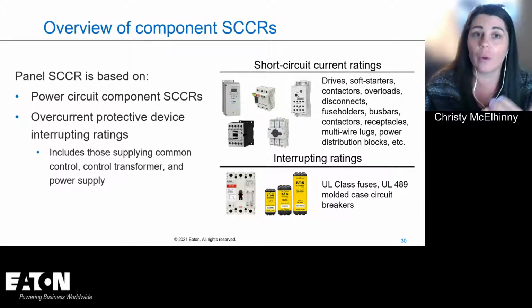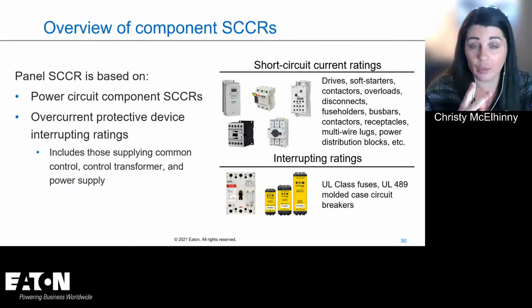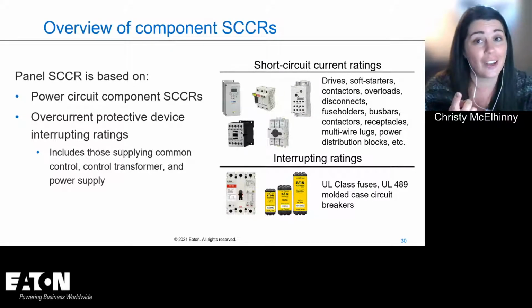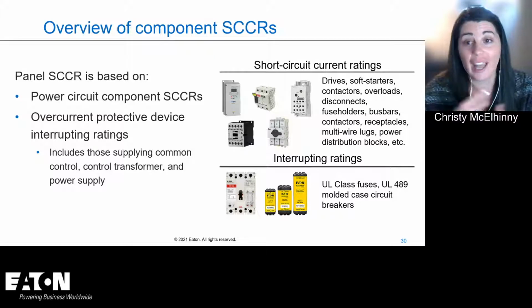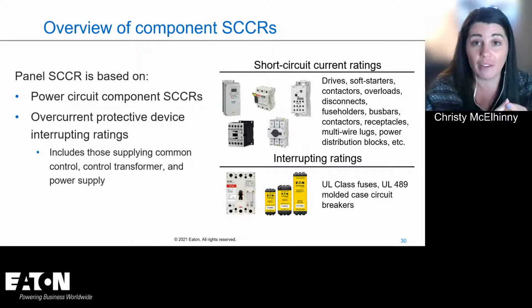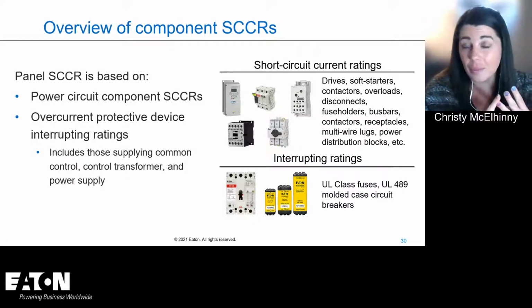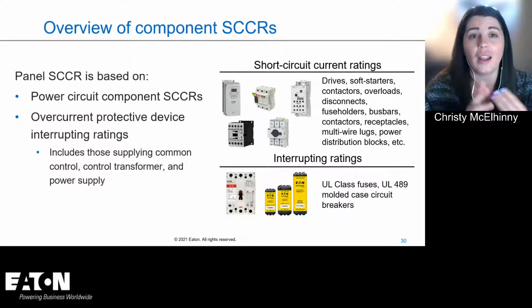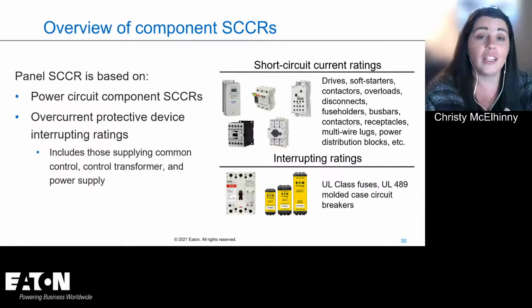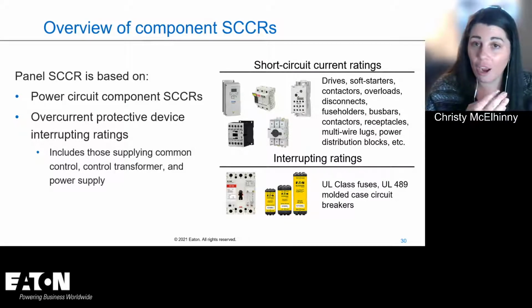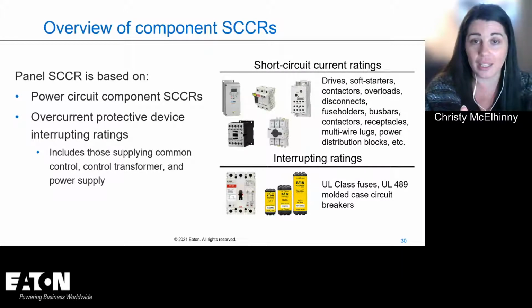So it's all of the power circuit components, those that feed loads. And they're going to have two ratings that we care about when we try to determine the short circuit current rating of a panel. It's going to be SCCR ratings or interrupting ratings. Now, we should already know the difference between these, but a refresher, right? Interrupting rating applies to my fuse, to my breaker, sometimes something like a manual motor protector inside an industrial control panel. That's the device that's interrupting the current. And it's really important to note that, by definition, the interrupting rating is the maximum amount of current that something can safely interrupt.